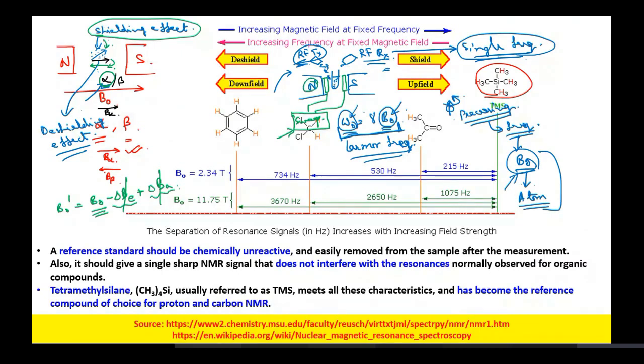The first one, these blue lines, this blue north and south, they are fixed ones, and that we call a permanent magnet system. However, the non-permanent magnet, which is helping us to sweep the magnetic field or increase the magnetic field in small incremental manner, helps us in overcoming the local magnetic field exerted by the electrons, and thereby helps us in bringing these protons into the alpha state.